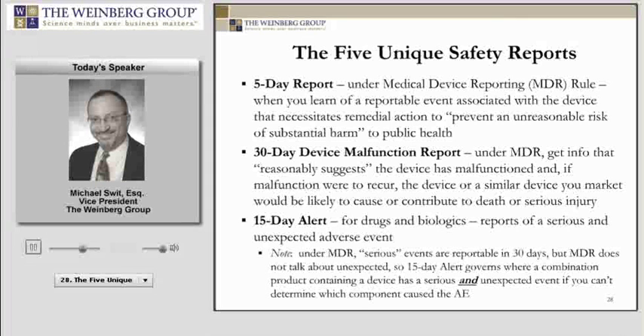For the drug and biologics world, one unique safety report is the 15-day alert. And this is where you have reports of a serious and unexpected adverse event. And most of you know that something is unexpected when it's not found in the labeling of the product. And the reason this can be important is because if you look at the 30-day device malfunction report and you have a combination product, serious events are reportable in 30 days under the MDR. But the MDR rules don't talk about an unexpected event. So technically, if you have a combination, which is a device and a drug or a device and a biologic, and you have an unexpected serious event, you can't rely on the 30-day device malfunction report. You have to go with the more rigorous approach of the 15-day alert.